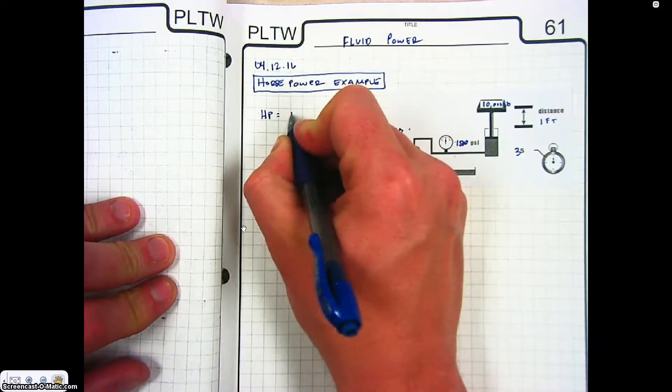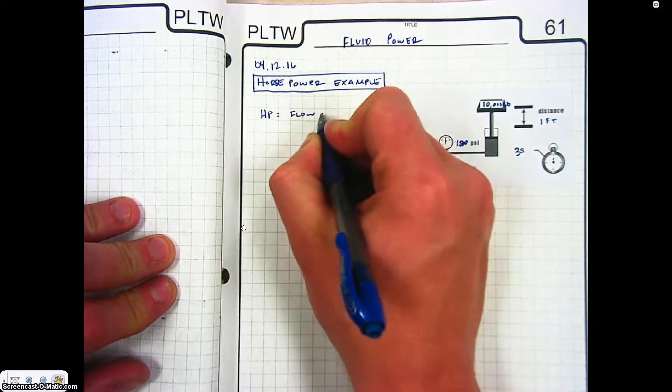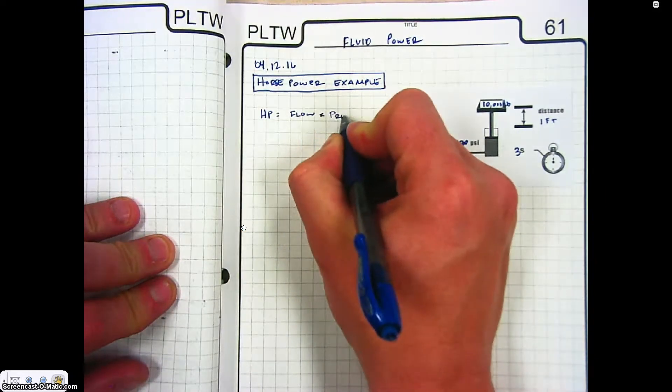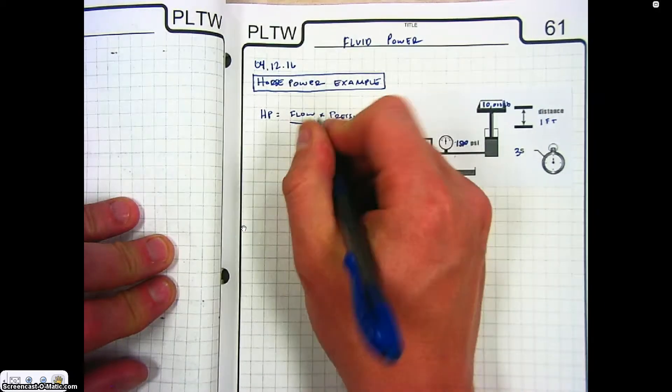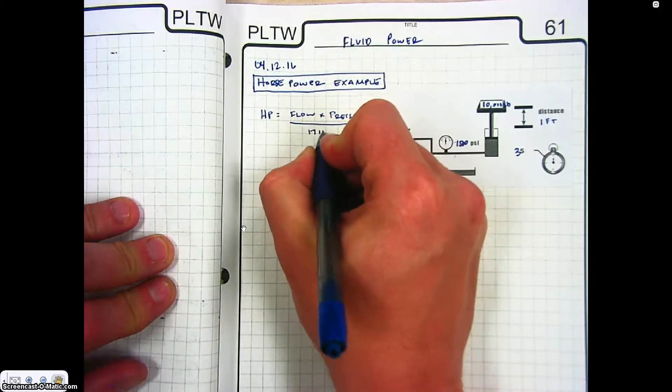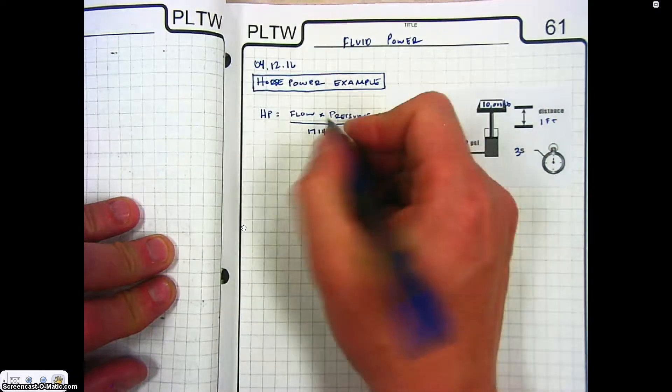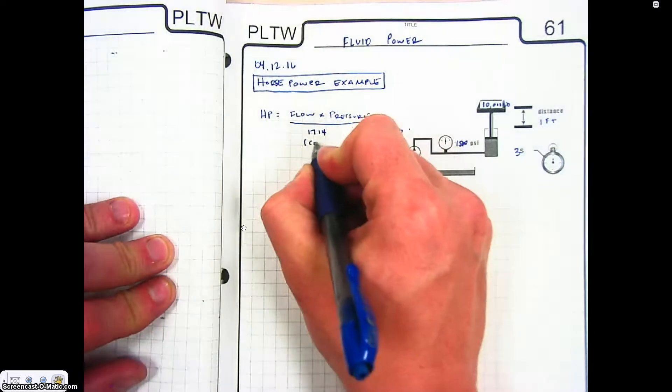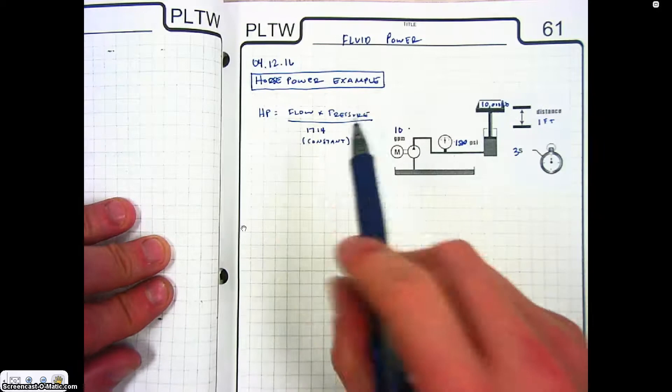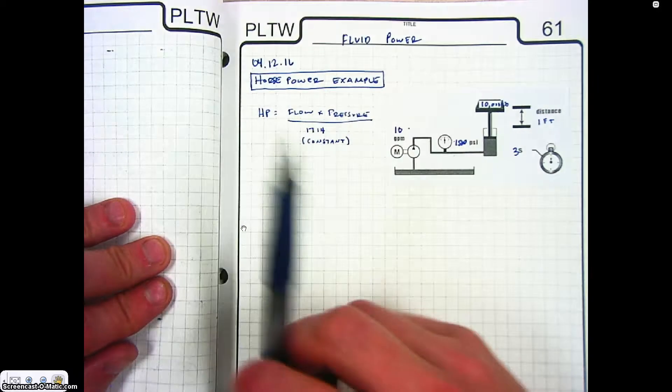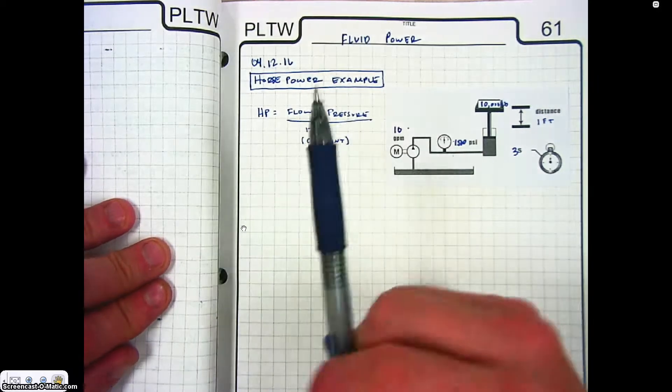Horsepower is equal to flow times pressure divided by 1714. 1714 is a constant number that gets us to the correct unit for that horsepower.